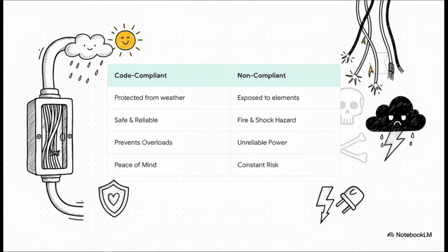And that clarity is what keeps safety professionals productive. If you're wiring a light post at 480 volts, you know you're in 225. If you're wiring a utility transformer connection at, say, 4,160 volts, you know instantly you're in 235. And the rules for clearances and signage are way, way stricter. Okay, let's synthesize this. The NEC 2023 is a deeply logical framework. It's built on a foundation of safety defined back in Chapter 2, wiring and protection. Yeah. And when power leaves the main building, Article 225 takes over, controlling both the big feeders and the smaller branch circuits running across your property.